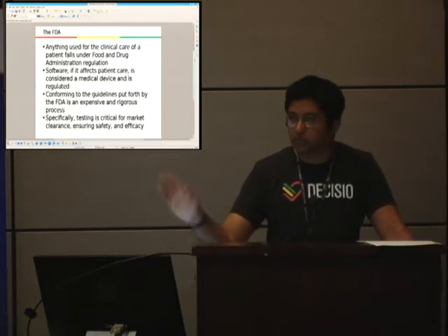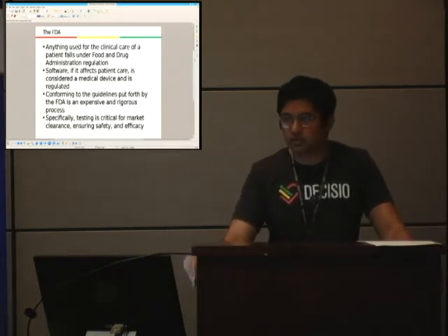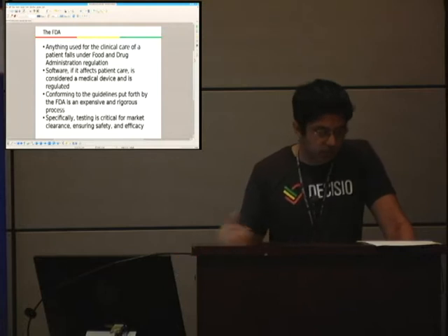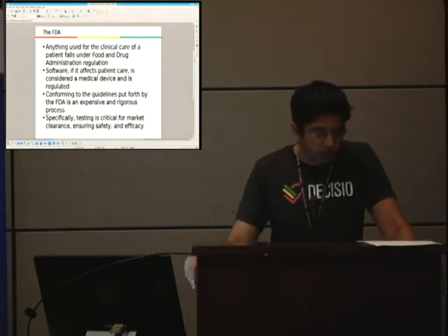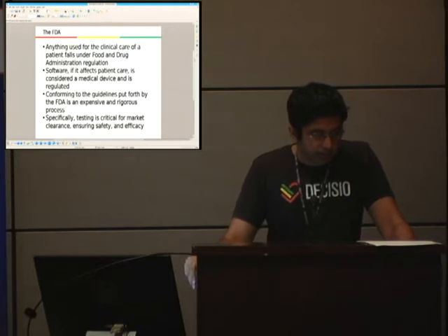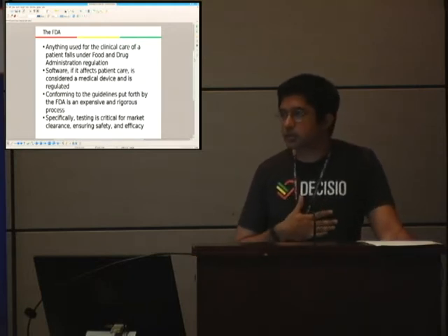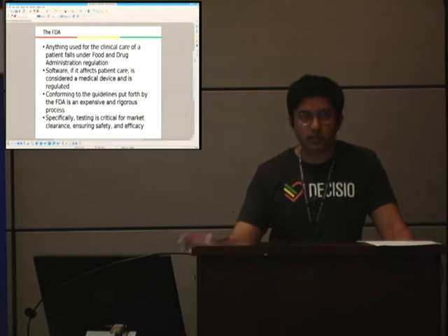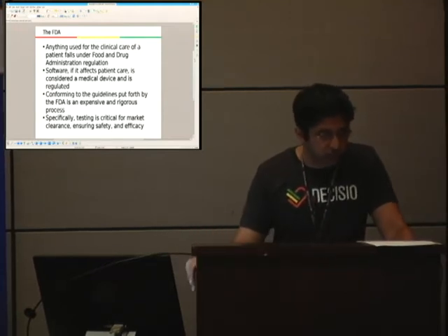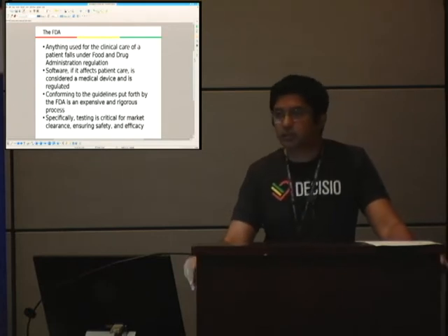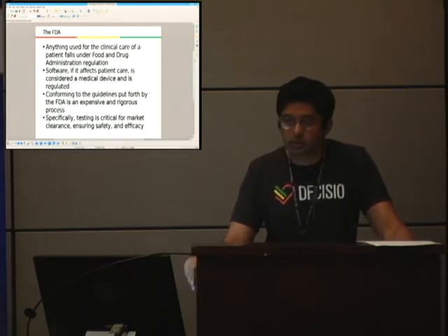So it's a very bizarre process. They're a very strange organization. What they look at for testing is different from what we would think from a logical standpoint. Even though software doesn't touch a patient, we don't administer medication or anything like that, they still consider it a medical device, and so you have to get it cleared. And they also don't have a sense of humor. If they don't like what you're doing, they're just going to shut you down.